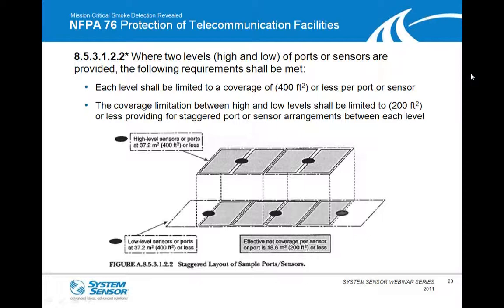Also, if we think about a data center where, as was talked about earlier, you might have two different levels of detection. So maybe you have a certain level of detection at the ceiling, but then you also have a certain level of detection at a lower level. Each one of those independently can be at 400 square feet of coverage, as long as when you combine the two, you do meet that 200 square feet for very early warning.